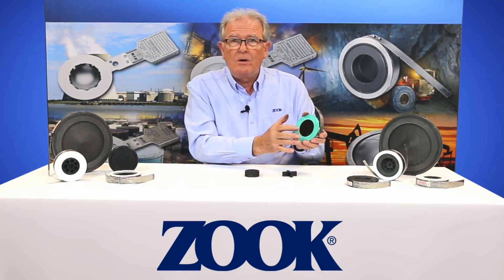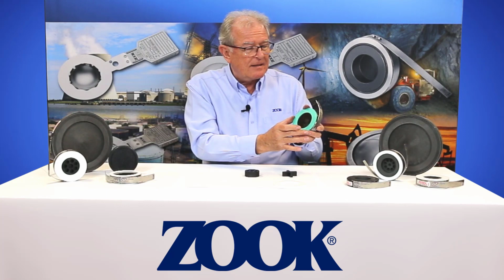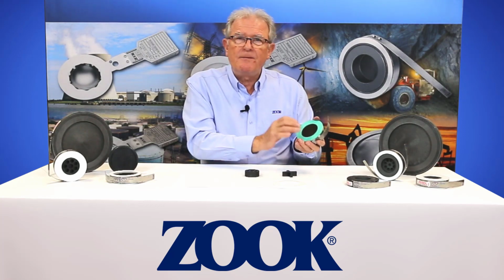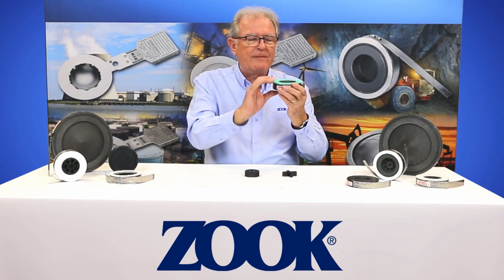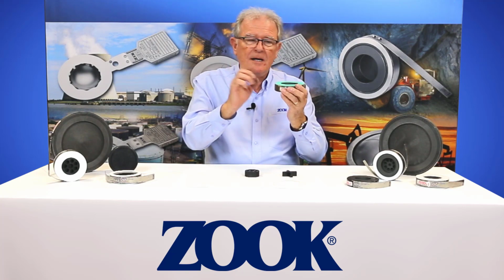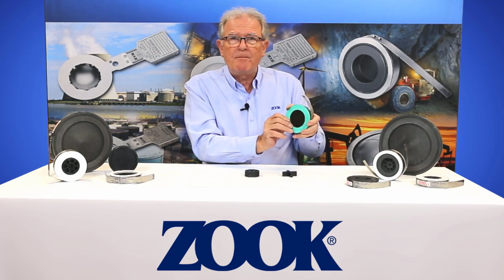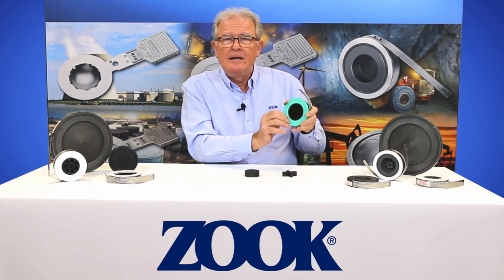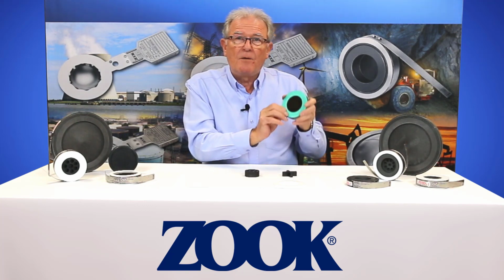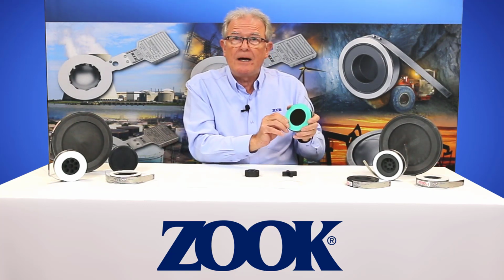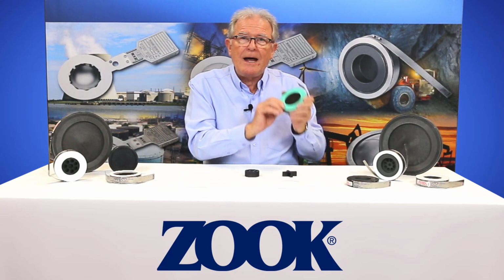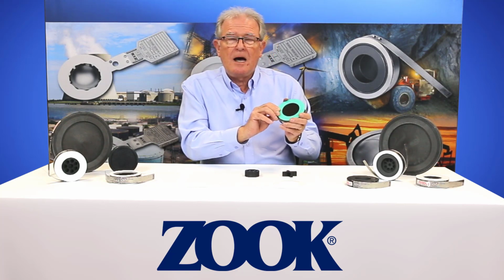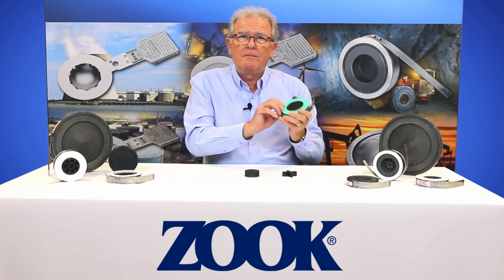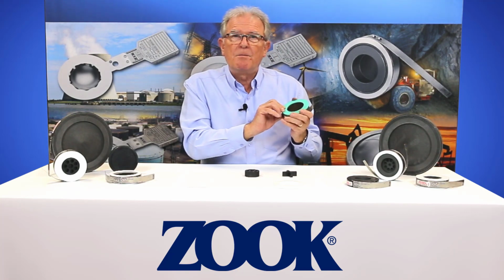If the bore, the ID of the gasket, is too small, it will interfere with the way that the graphite disc ruptures. If you are supporting the membrane by having a smaller ID, then the burst rating of the monodisc will be much higher. So it is critical you have the correct size gaskets, and I implore that when you buy monodiscs from ZOOK, you buy them with the gaskets attached.